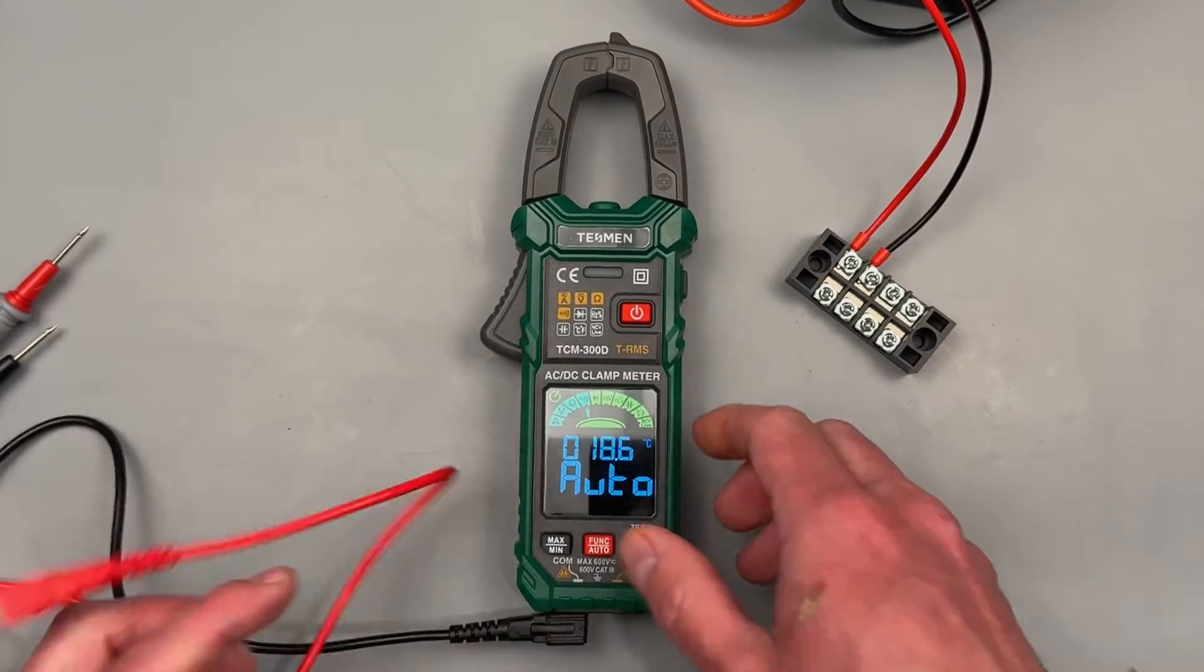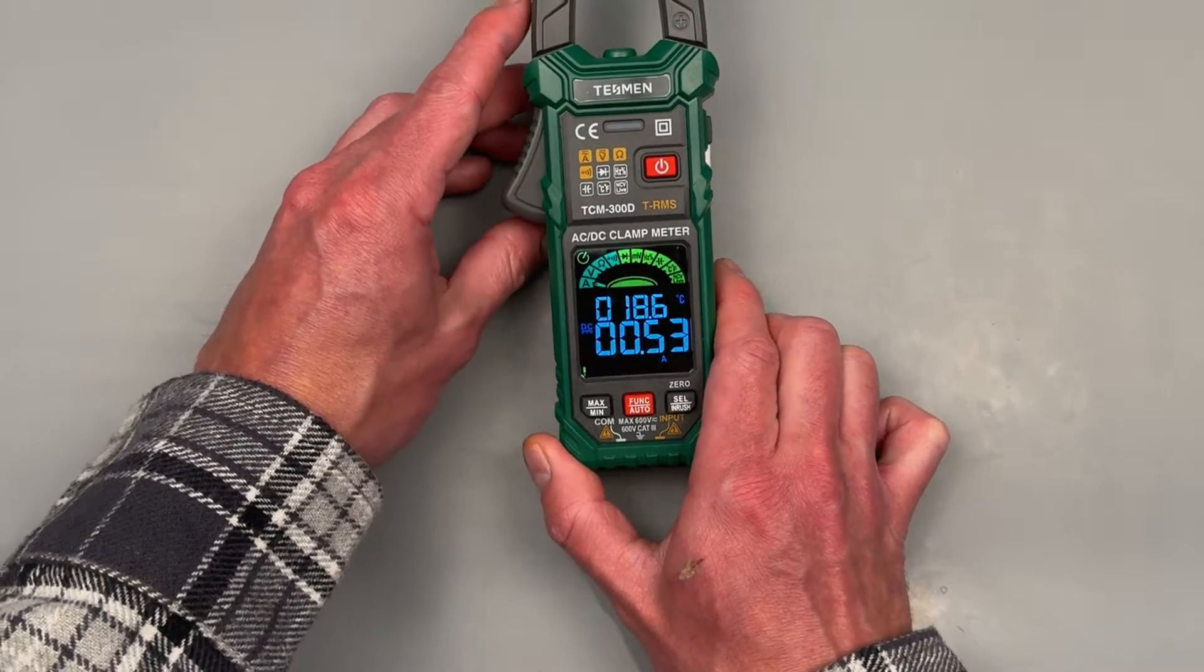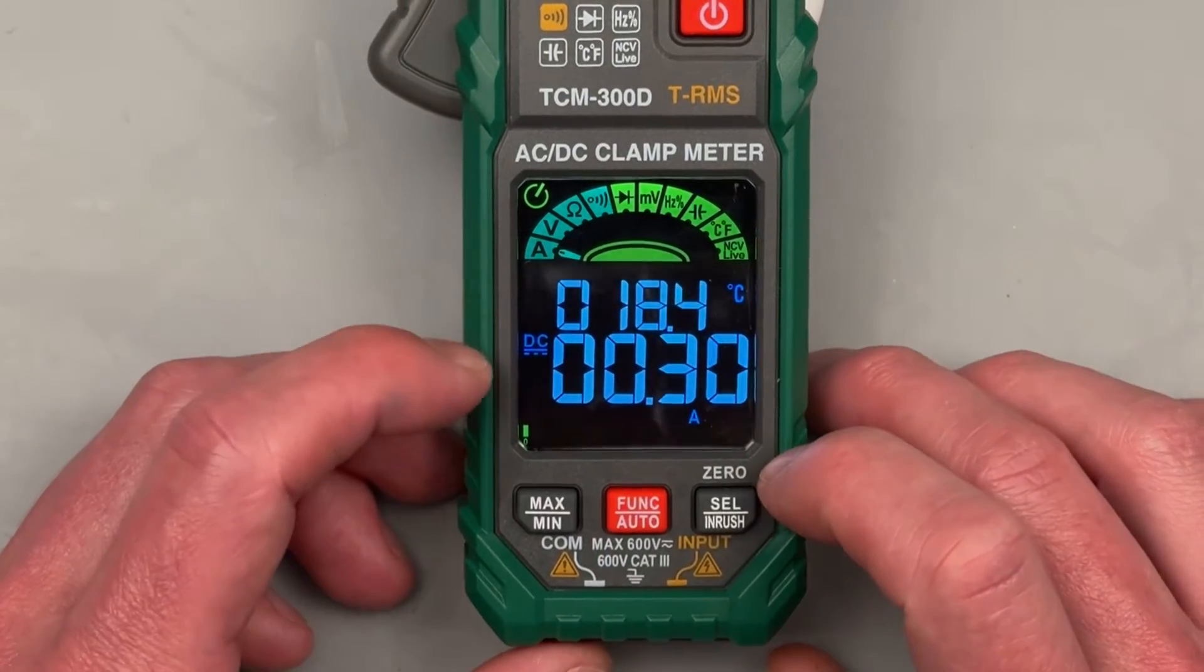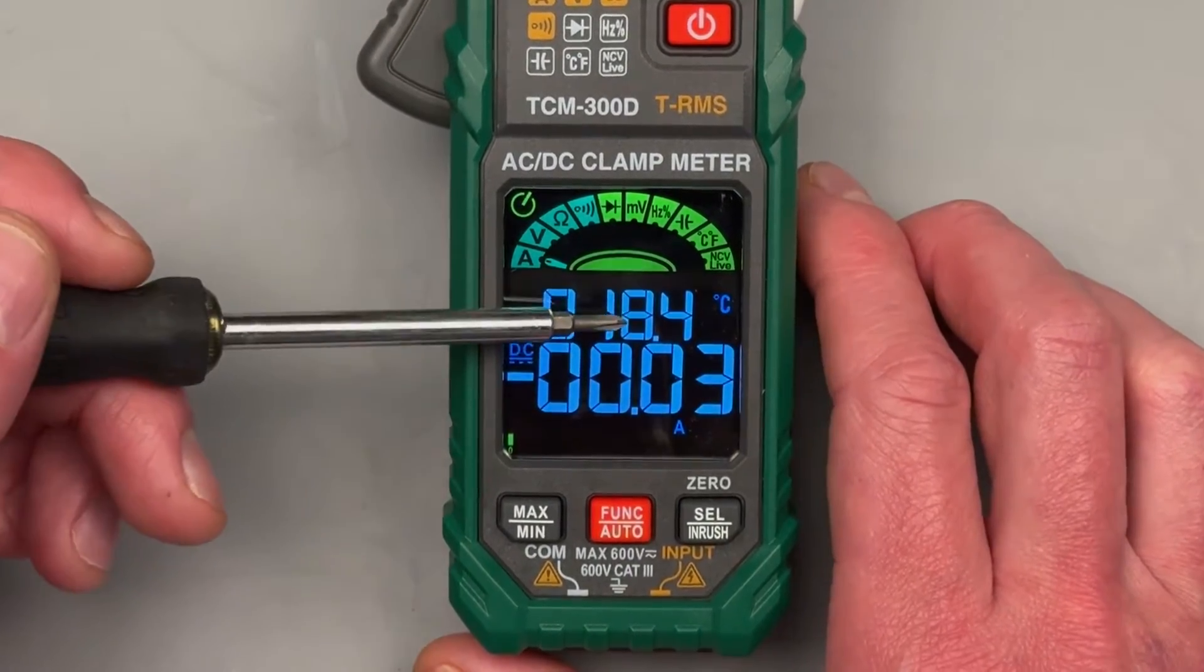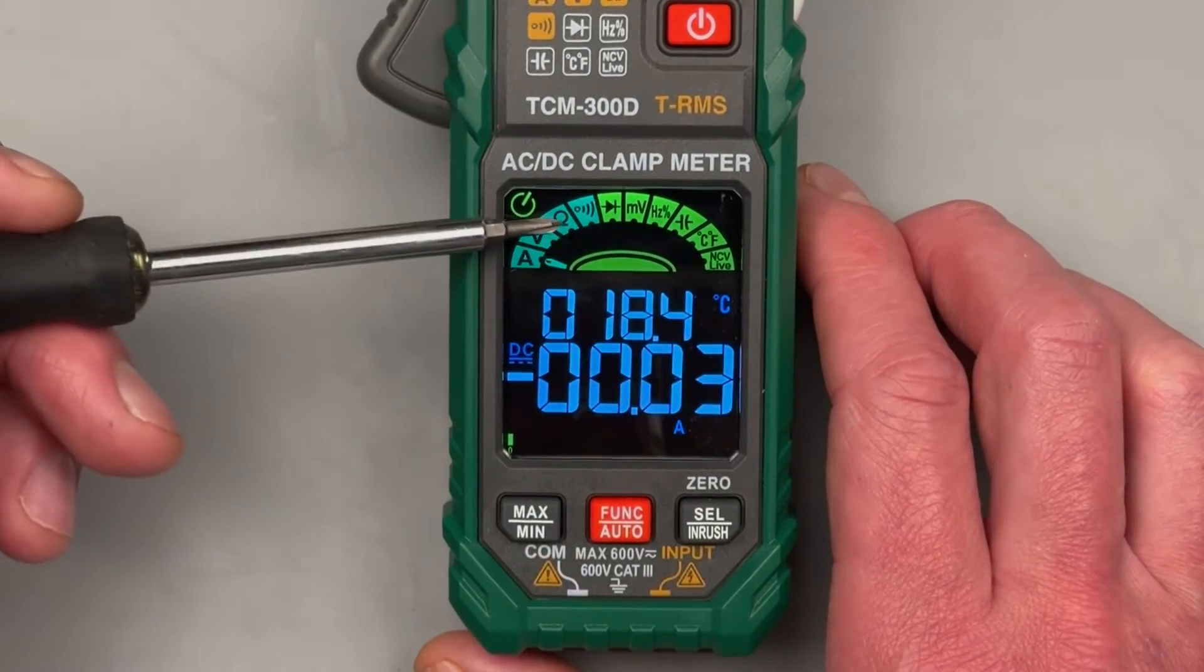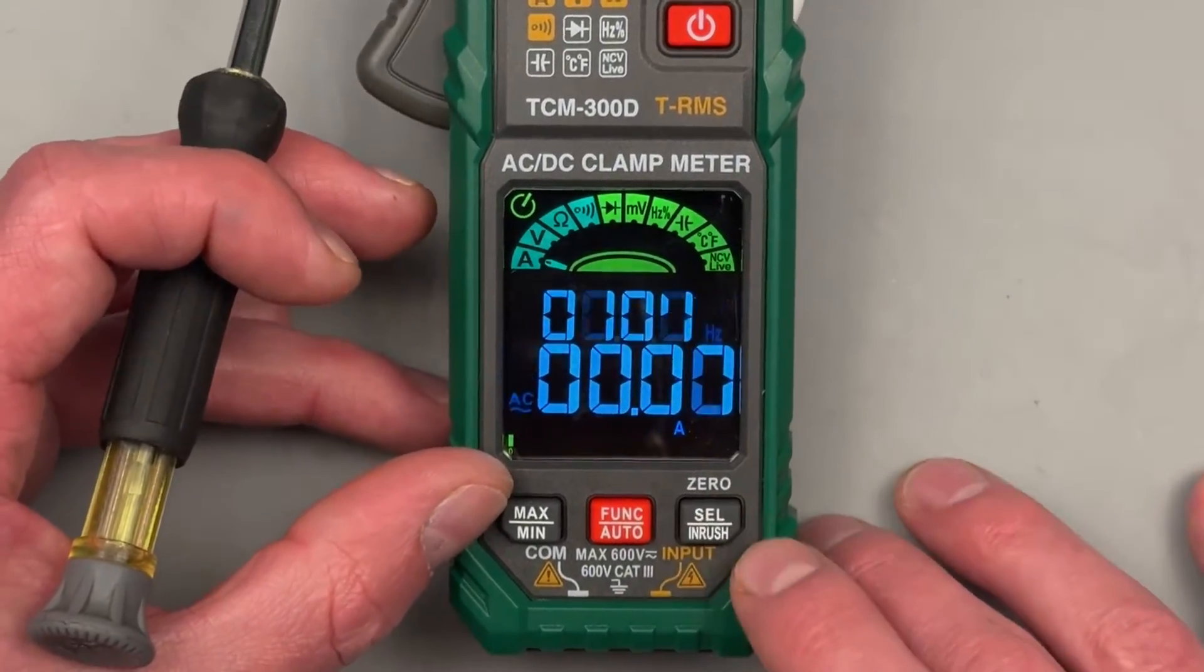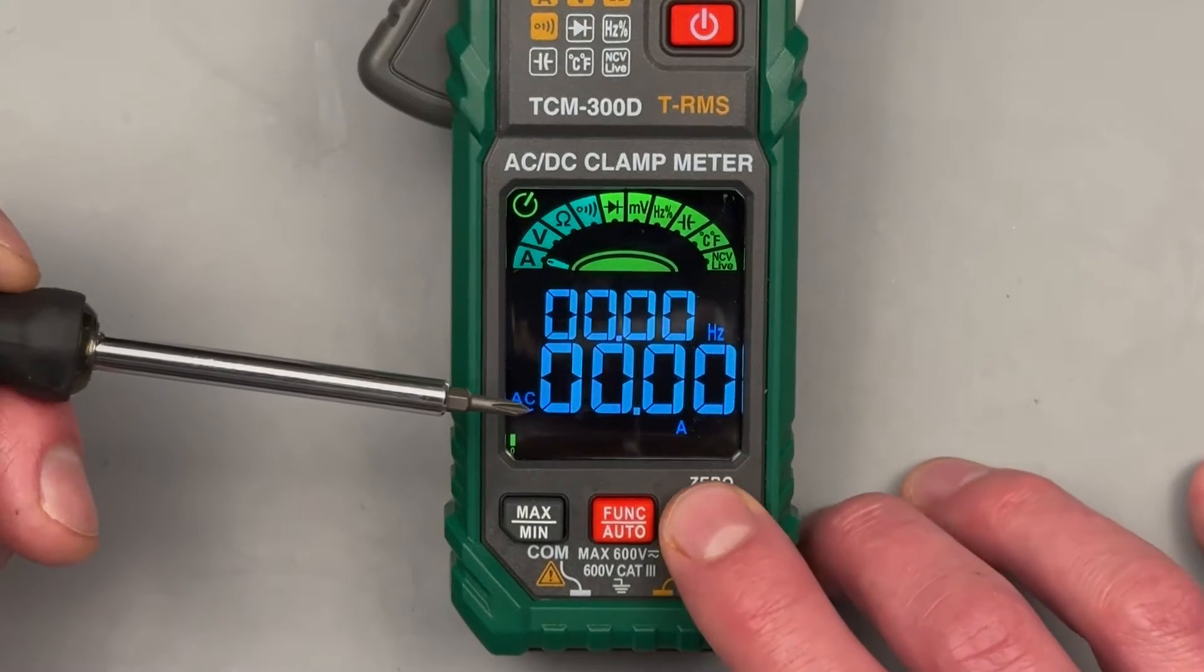But let's go ahead and start at the beginning. The main function or main marketing point of this meter is going to be its inrush amp clamp capability. It's going to default to DC amperage. This secondary display up here is going to display ambient room temperature in Celsius, and then sometimes it'll be in hertz. It'll change depending on the setting that you're in. We're on DC amp clamp. Hit selection, now we're in AC. Notice how this top portion has changed to hertz.